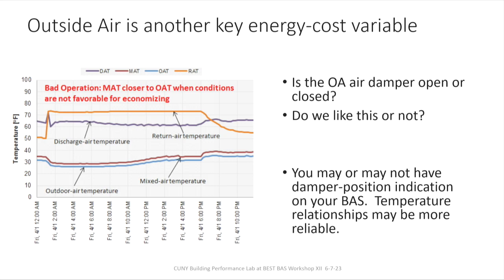The other thing that I find, from a control standpoint, that's really scary is this mixed air temperature is dropping below 30 degrees. If your mixed air is dropping below 30 degrees, you're at risk of freezing coils and damaging systems. So that's another thing that, from my perspective, should be shutting this unit down in an emergency state. Yeah, you're going to have an alarm on this. So actually, Robert, you jumped my next question. So the outside air damper is open, do we like this or not? And you're right, at these temperatures, we are in freeze hazard.